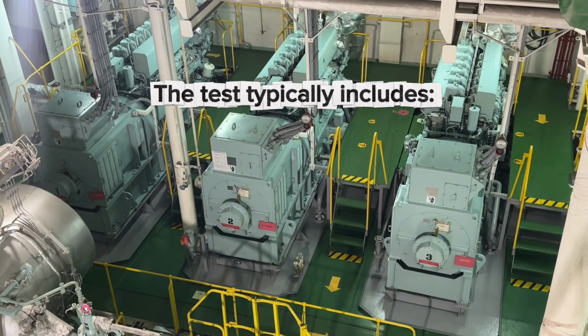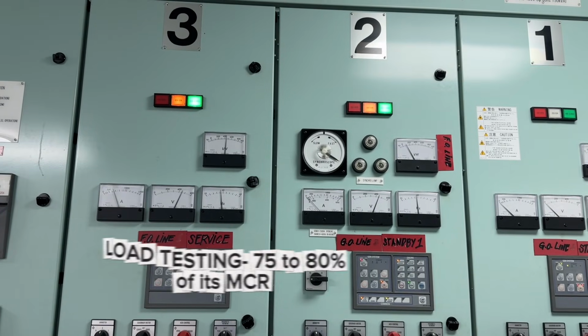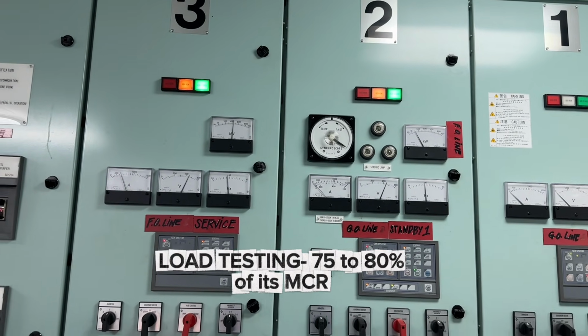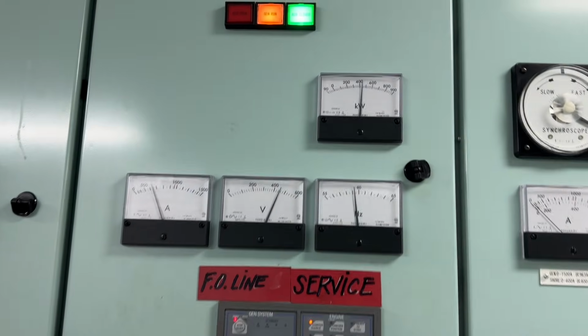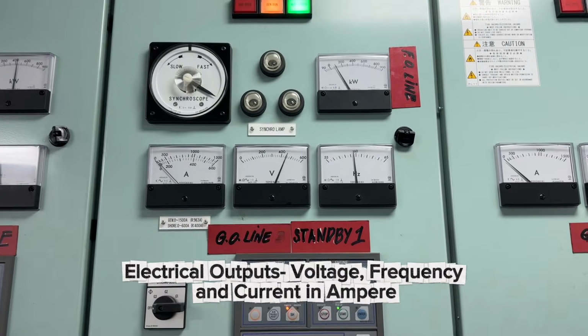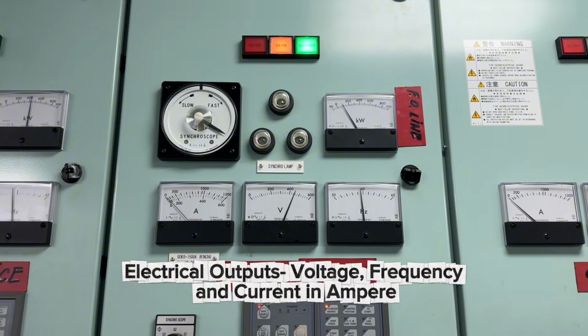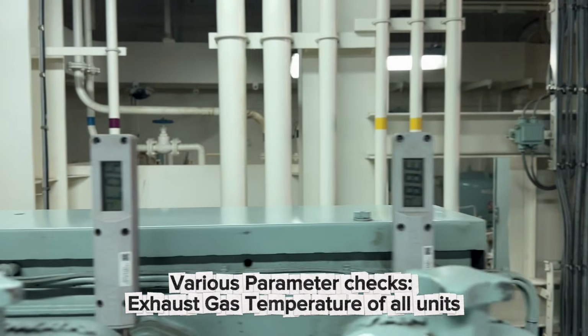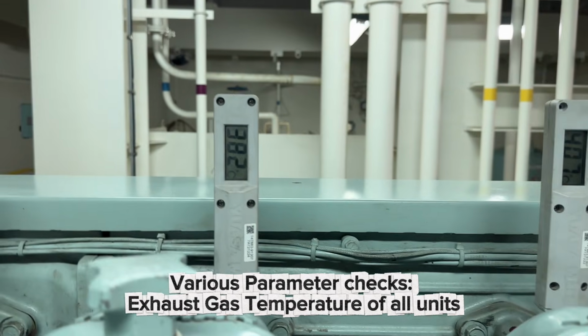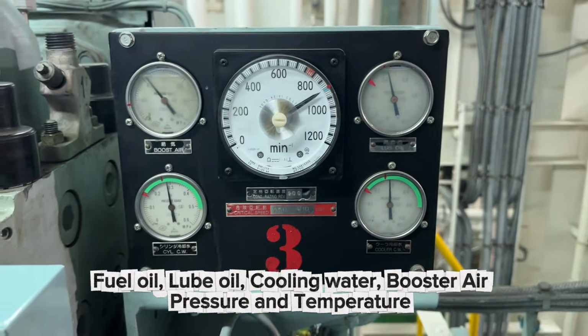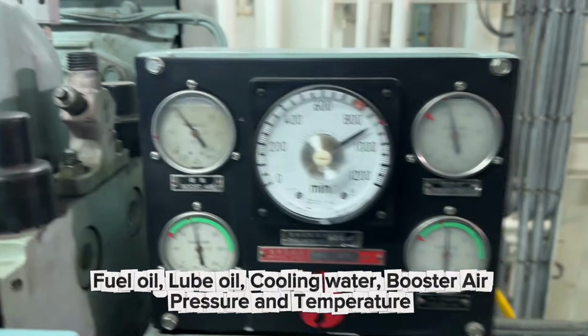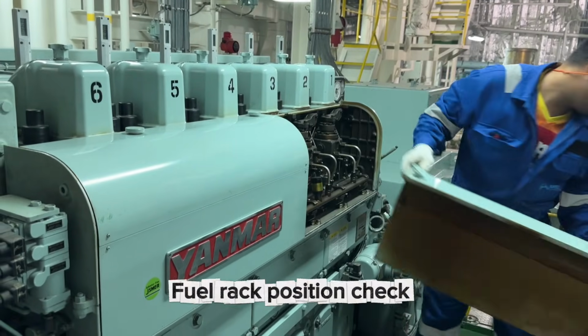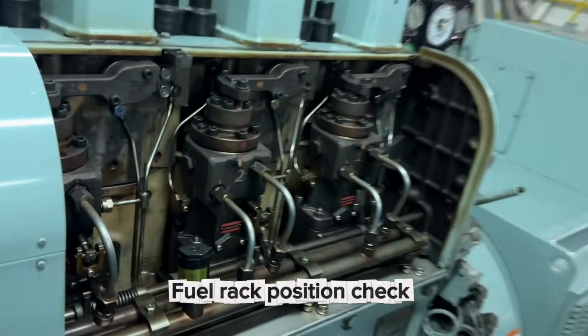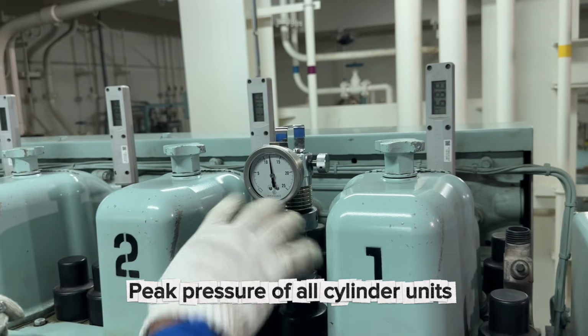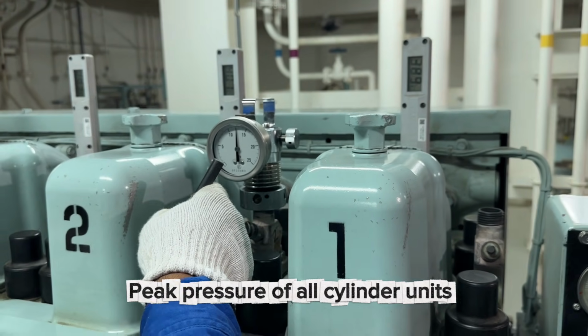The test typically includes load testing under 75 to 80% of its MCR, or maximum continuous rating, electrical output checks like voltage, frequency, and ampere, and various parameter checks like exhaust gas temperature of all units, fuel oil, lube oil, cooling water, booster air pressure, and temperature. It also includes the fuel rack position of its pump and, most importantly, the peak pressure of all cylinder units.